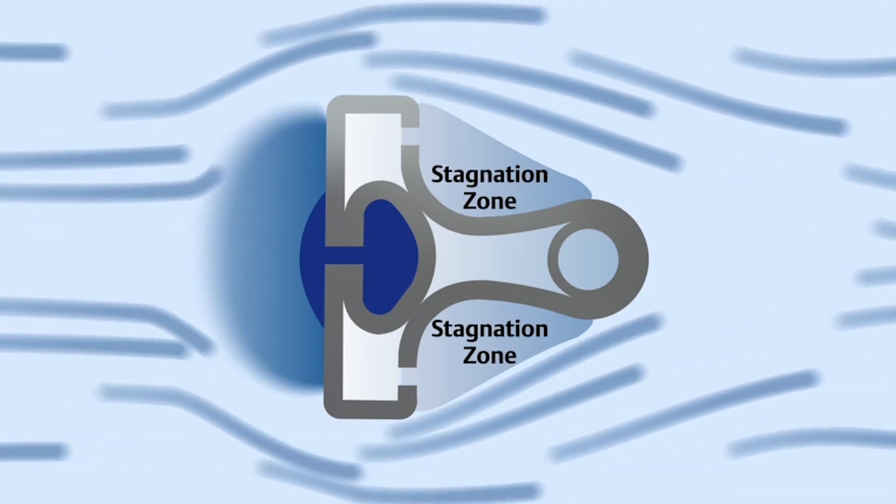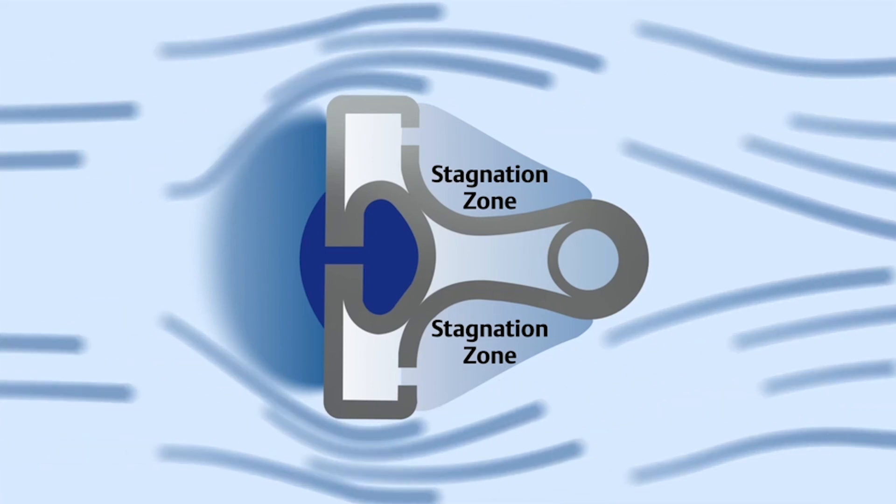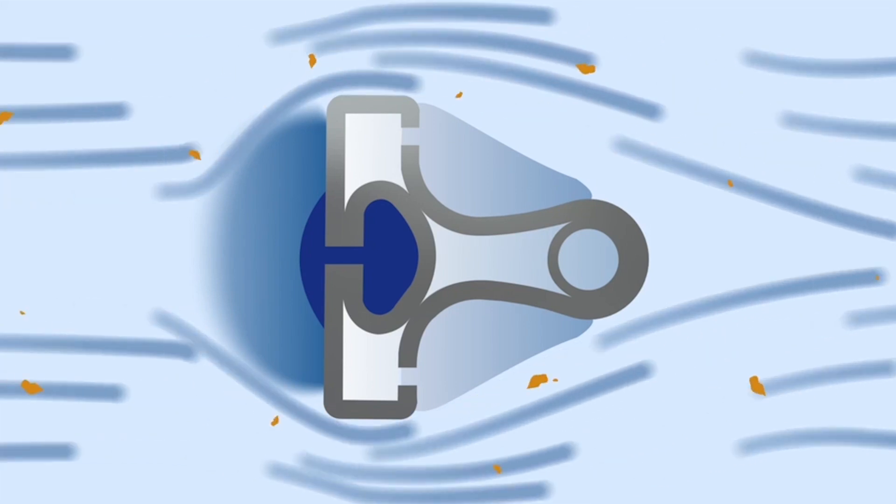Stagnation zones on the back side of the T-shaped sensor are positioned to reduce the noise and measurement inaccuracies that lead to process variability, as well as keep particulates from clogging the low side pressure ports.